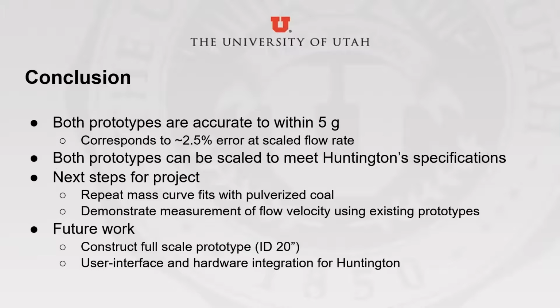Comparing these two sensors, we see that they're actually both accurate to within 5 grams, which corresponds to about a 2.5% error at the scaled flow rate. We've discussed with PacifiCorp engineers and confirmed that both prototypes could feasibly be scaled up to the full pipe size at Huntington. We plan on repeating these capacitance versus mass calibrations using pulverized coal in the coming weeks.